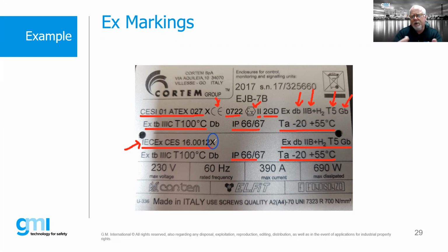So if we go and install a bunch of glands and we don't pay attention to that X condition, and somebody like me walks out to that facility and sees all these glands that haven't been clamped within 300 millimeters, and it's stated very clearly on their certificate, then that's a major issue. So always, always, always pay attention to the X condition.